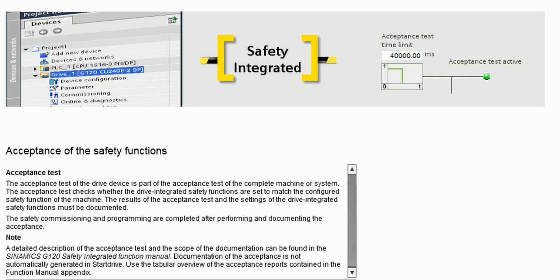Acceptance test. The acceptance test of the drive device is part of the acceptance test of the complete machine or system. The acceptance test checks whether the drive-integrated safety functions are set to match the configured safety function of the machine. The results of the acceptance test and the settings of the drive-integrated safety functions must be documented. The safety commissioning and programming are completed after performing and documenting the acceptance.